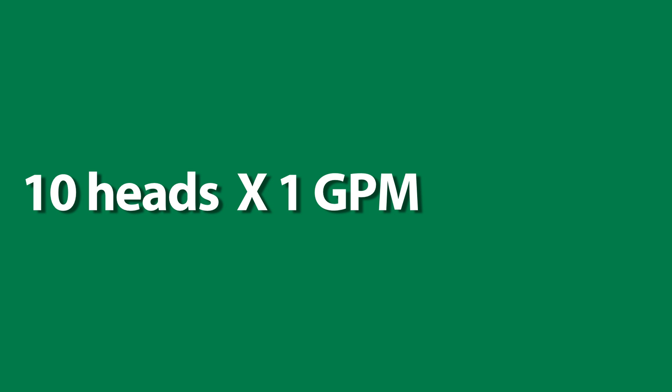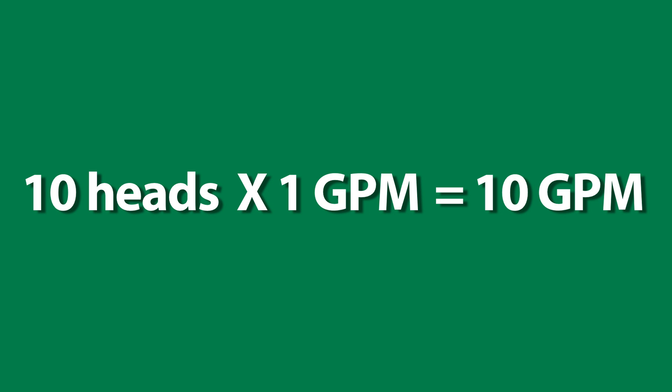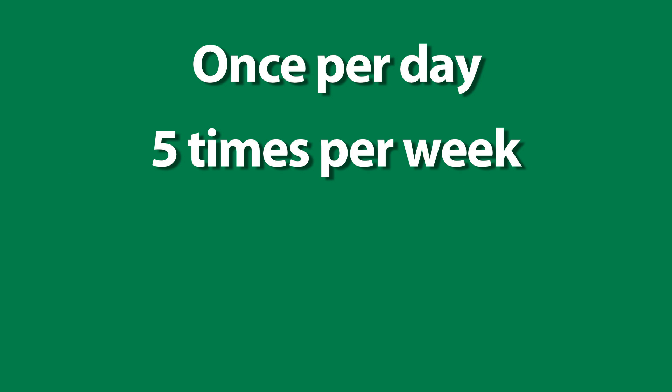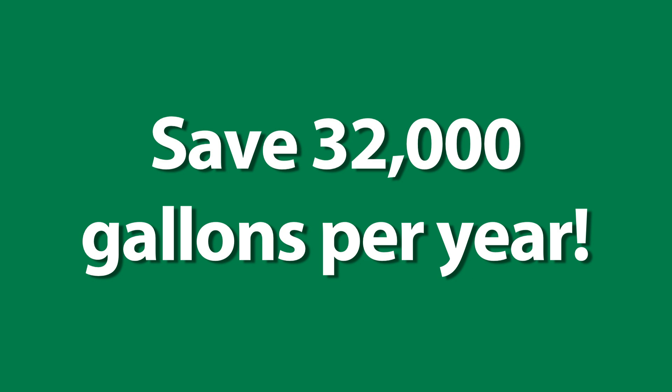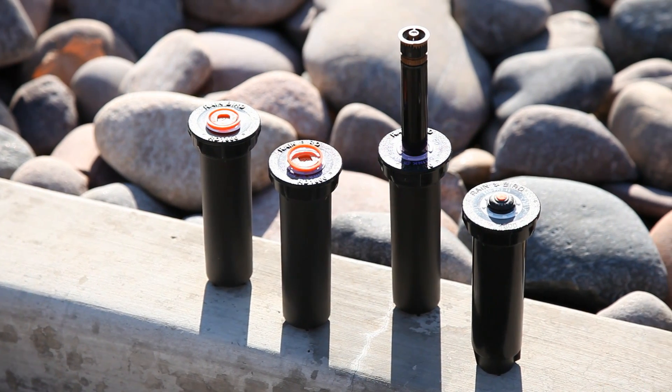If a sprinkler zone has 10 heads, each using one extra gallon per minute, you would be wasting 10 gallons per minute. If this system ran once a day, five times a week, 15 minutes per cycle over 40 weeks, you could save approximately 32,000 gallons of water per year by using Rain Bird PRS spray heads.